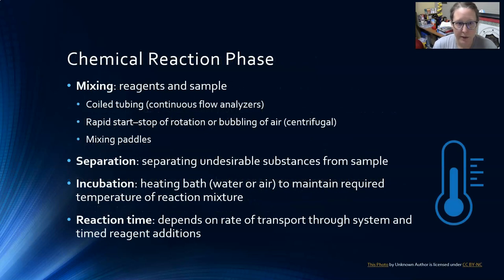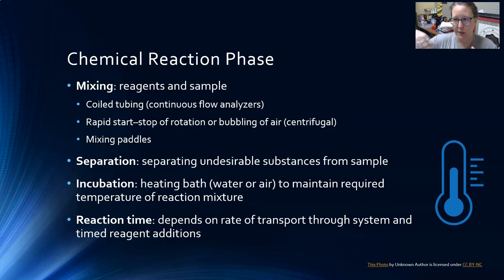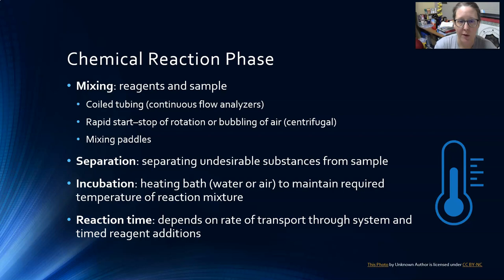Next is the chemical reaction phase. First is mixing the reagents and the sample. In large analyzers there are probes dealing with samples and probes dealing with reagents, adding things to reaction vessels or cuvettes. There are different ways reagents and samples can be mixed depending on the system. In older continuous flow analyzers, coil tubing can be used to mix them.